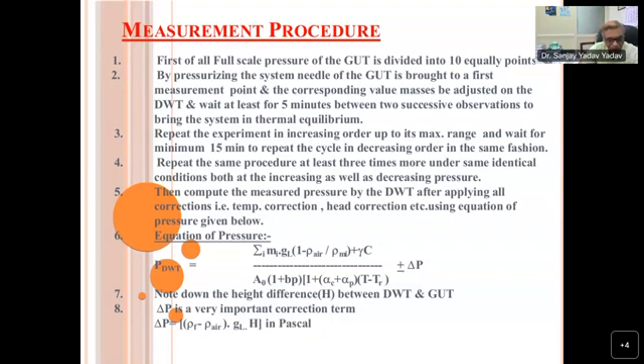And this delta P, how to calculate? Rho F is the fluid density minus rho air. So basically this is very dominant in hydraulic, because rho air is around 1, but fluid density is around 900. So when 900 minus 1 is again equivalent to 900, this will make a big difference in hydraulic. But in pneumatic, any gas must also be having around 1. 1 minus 1, it is negligible. So that way this correction is sometimes avoidable in gases, but in hydraulic this should not be avoided.